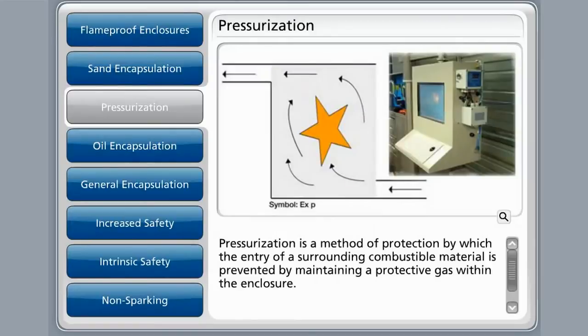Pressurization is a method of protection by which the entry of surrounding combustible material is prevented by maintaining a protective gas within the enclosure. This is generally accomplished by creating a higher pressure within the enclosure than the surrounding atmosphere. This protective method would be used for any power-operated equipment.